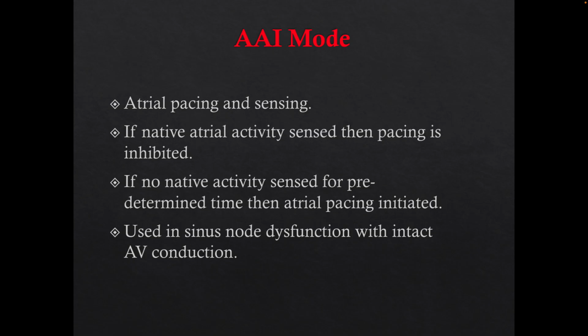So what it does is AAI: pacing is the first, sensing is the second, and I is inhibit, which means if there's a sensed beat, if there's a P wave, because this is all about atrial activity now, then it won't deliver a pacing output. But if there's no P wave, so if it's set at AAI 60 and the intrinsic or native rhythm is dropping below 60, the device will kick in to pace. And patients don't feel this typically. They should not. The only time that they might feel it, obviously, like I said, is transcutaneous pacing. It is rare. Patients may sometimes feel pacing, but it's not common at all.